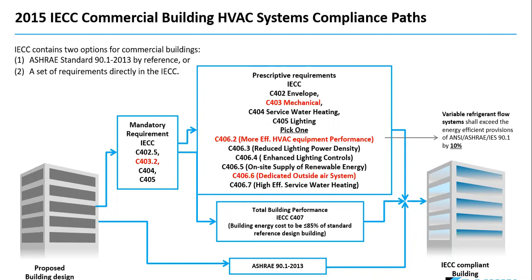The way that VRF systems are compared and managed through IECC entails reviewing section C403 for mechanical, then going to C406.2, which calls for more efficient HVAC performance. By definition, we're looking for VRF systems to be at least 10% more efficient. And then we also look at the secondary path, which you can see at the bottom of the screen, ASHRAE 90.1-2013. So engineers will utilize one of these paths to define how the VRF system will be applied to a building.